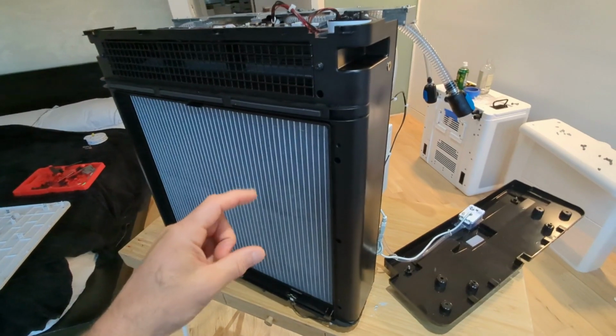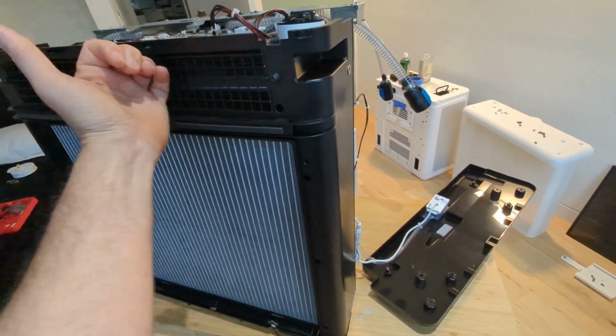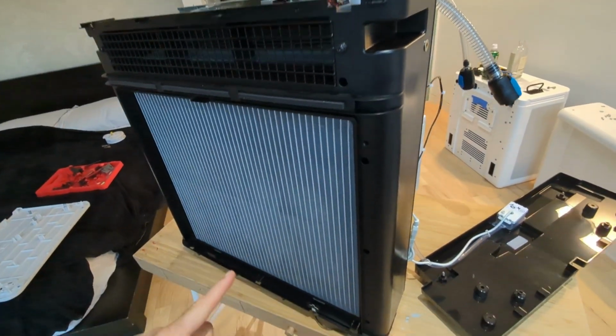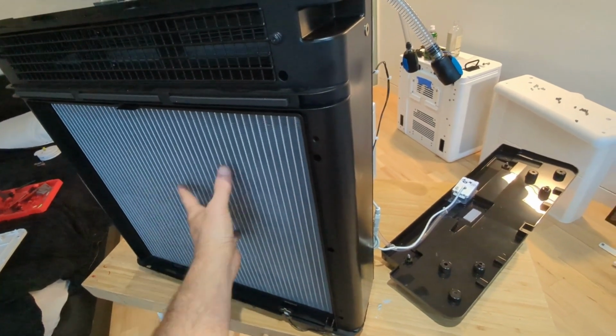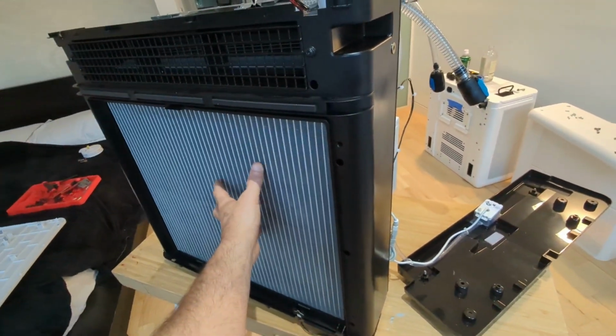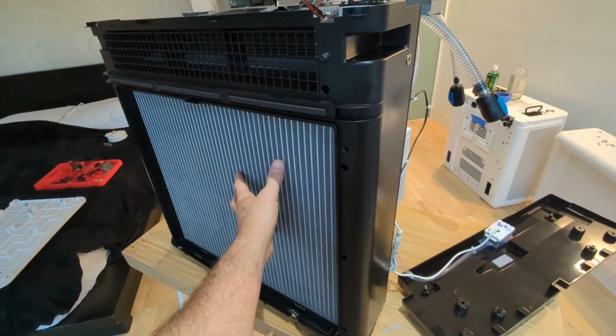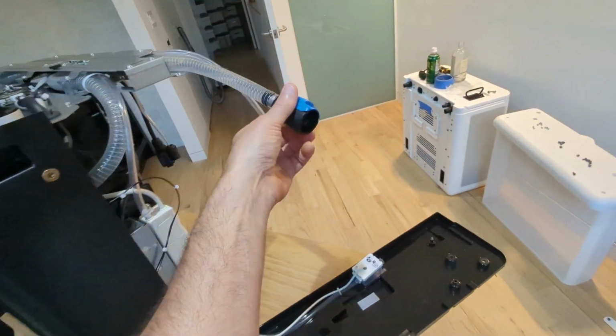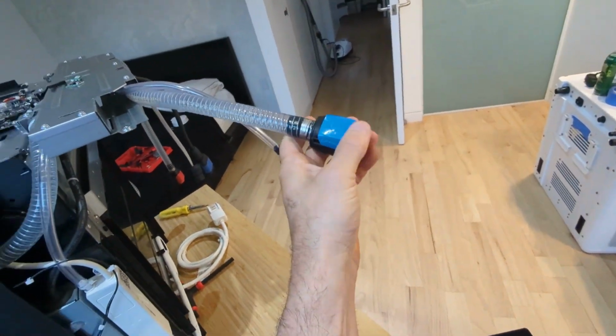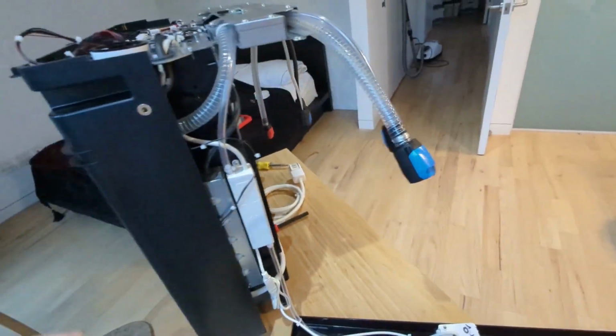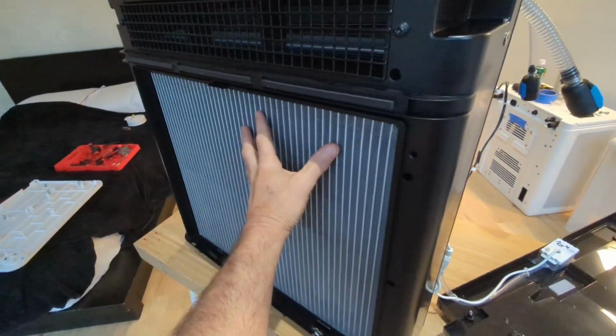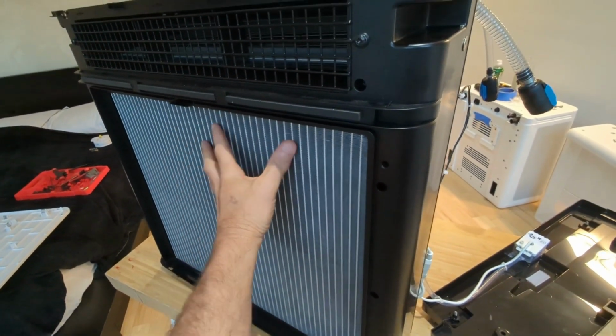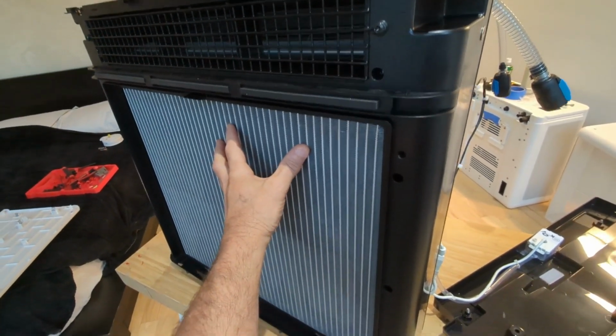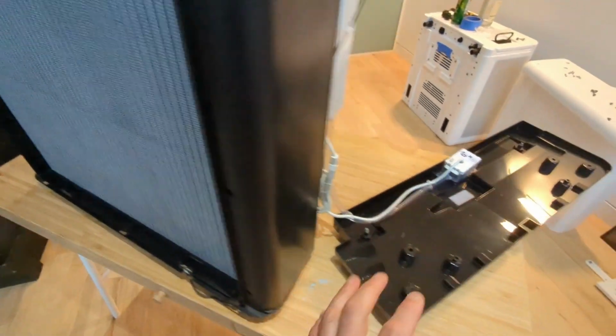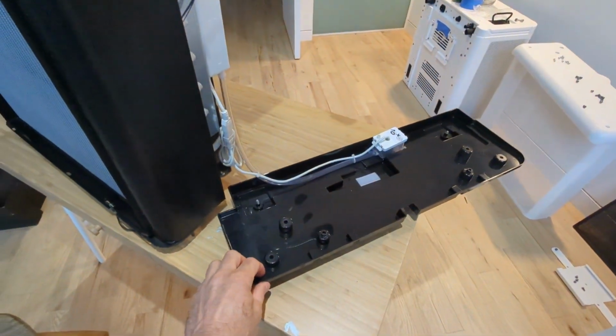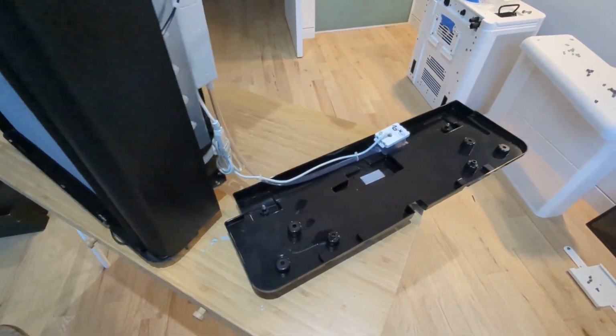Here's the indoor side, which is just a glorified fan coil. Here's the fan that is blowing air out into the room and sucking room air in through this coil, where it's either going to get heated or cooled depending on the temperature of the coolant that's running through these lines. Again, those really nice no-leak click connectors. When this is in air conditioning mode, this coil is going to be cold, and you're going to have warm, moist air going over it, so water is going to condense out of it and drip down here into this condensate collection pan, which is normally underneath here to catch that water.